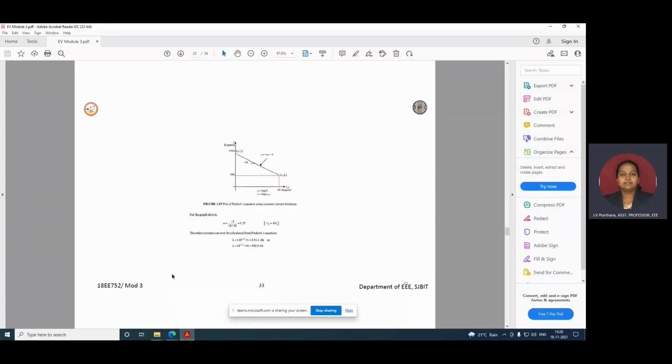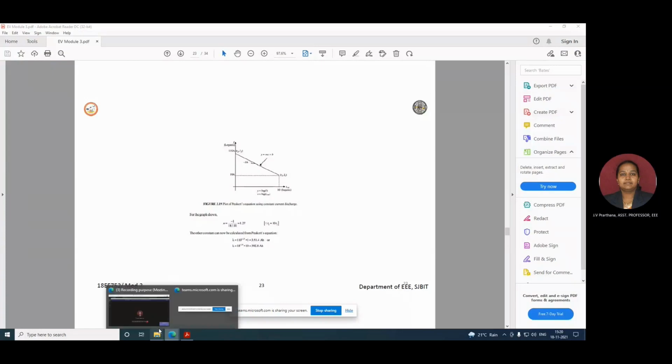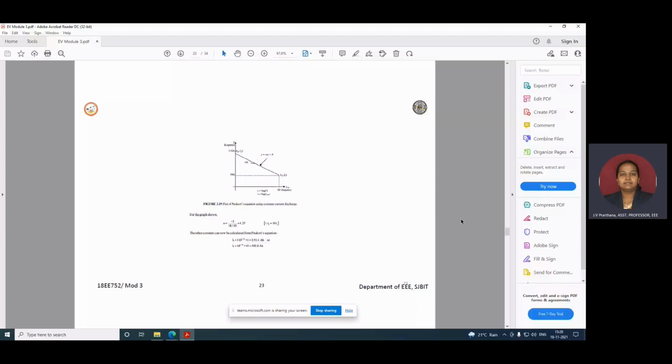This law has its own limitations. The first one is the effect of temperature on the battery is not included in the equation. We do not see any temperature dependencies in the equation. Secondly, the battery age is not considered. The Peukert exponent increases with the battery age. Thirdly, if calculating for a low discharge rate, the equation does not account for the fact that each battery has a self-discharge rate. In terms of estimation, Peukert's law gets much closer to estimating real-world performance of the battery than simple extrapolation of the ampere-hour rating.